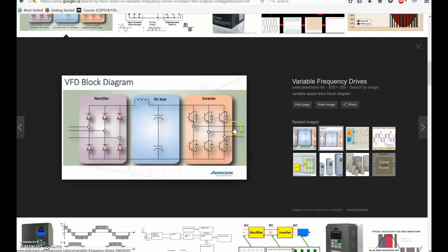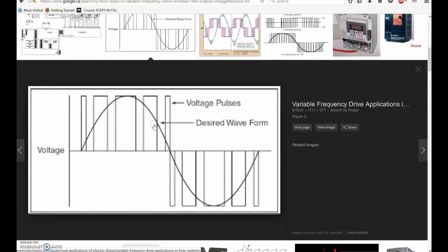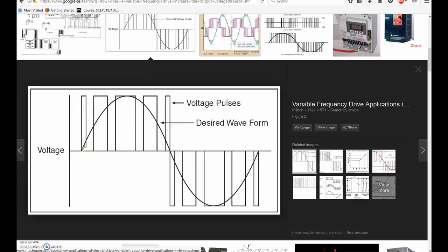Transistors fire the DC to the motor. The voltage turns on and off in DC square waves sent to the coils. But the coils have that ELI property — voltage leads and current lags — so the inductance of the motor coil smooths this out. Instead of getting a square wave for current, the coil produces a nice smooth sine wave for the current.